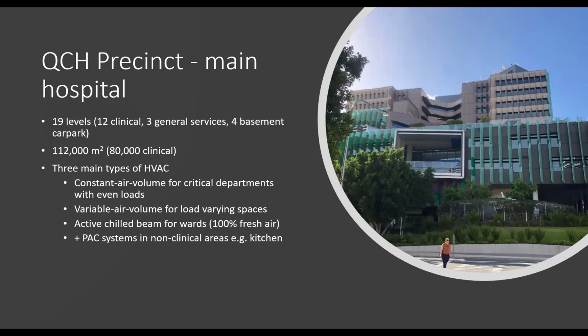Constant air volume systems serve critical departments with fairly even thermal loads, such as operating theatres. Variable air volume systems serve load-varying spaces such as open reception areas and clinic spaces. Active chilled beam systems serve the wards, which are supplied with 100% fresh air. There are also a number of packaged air conditioning systems for non-clinical areas such as the kitchen.